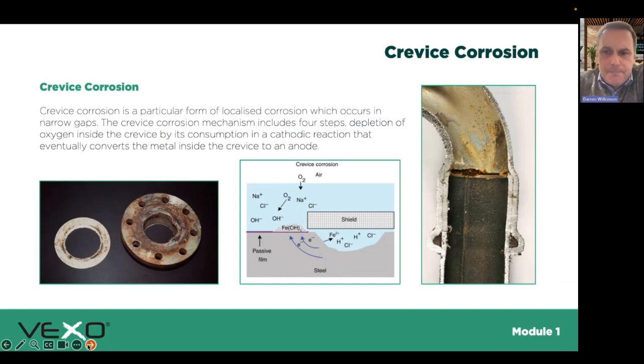We have crevice corrosion. So again, it's this relationship between the amount of oxygen in one location to the other. If we have a crevice, a bit of a dead leg, for example, we're going to see again a drive in the chemical reaction at that location. In the photograph to my left, or to your left as you look at it, there's a flange, and you can see the damage that's occurred there. It would appear that when the flange was bolted together, it wasn't bolted together opposingly when tightening up the nuts, a bit like putting a car tire on. Otherwise you won't get a nice firm flush seal, and you allow for this crevice to occur.